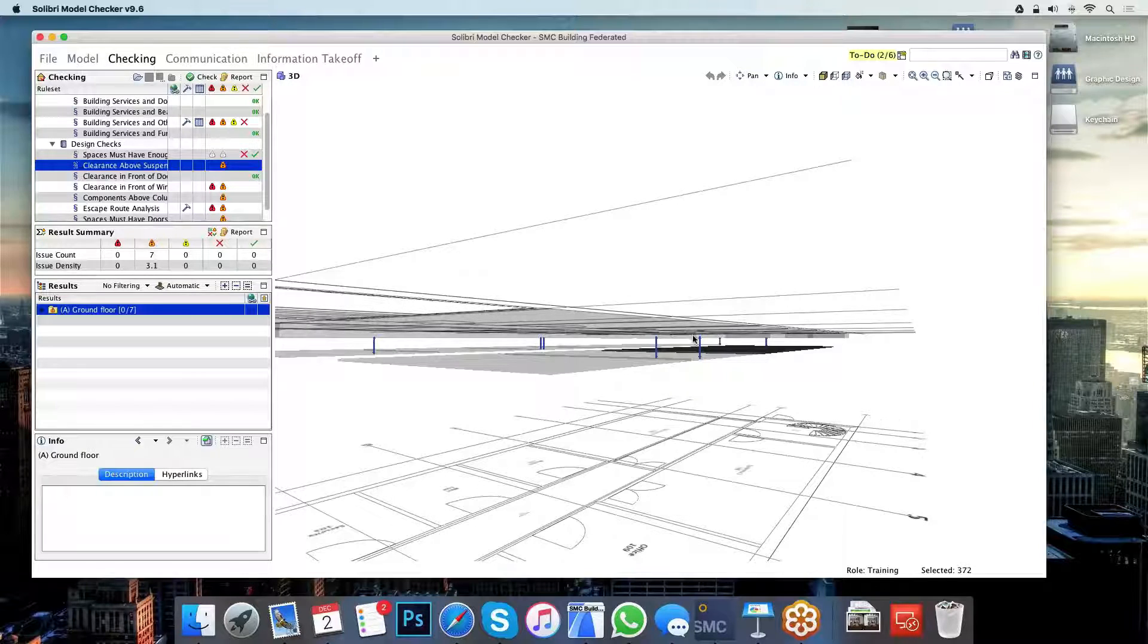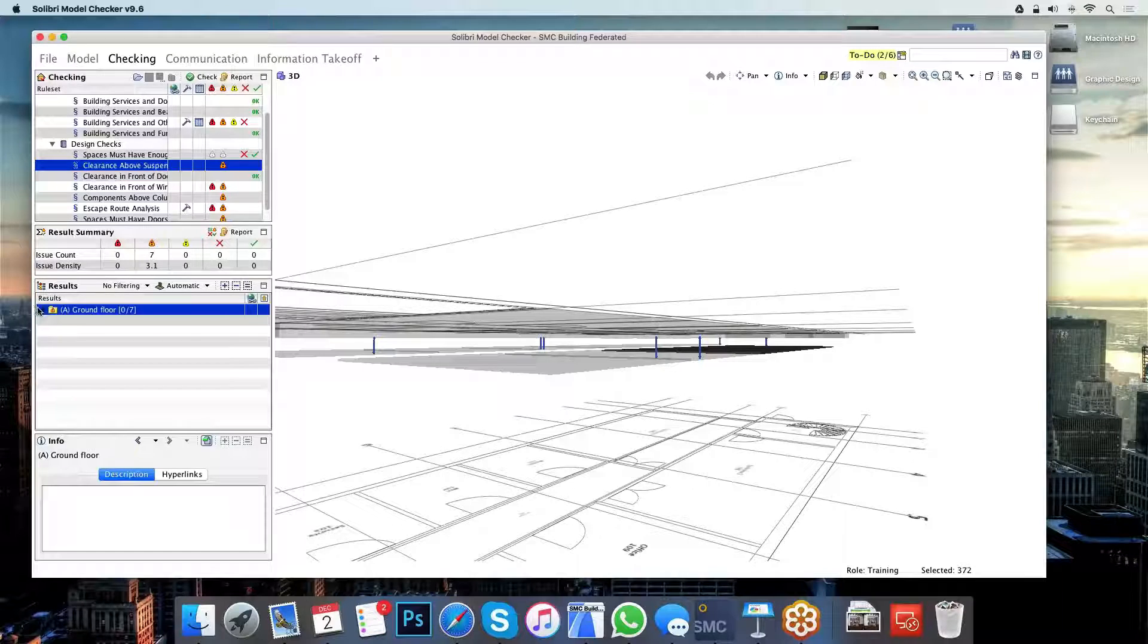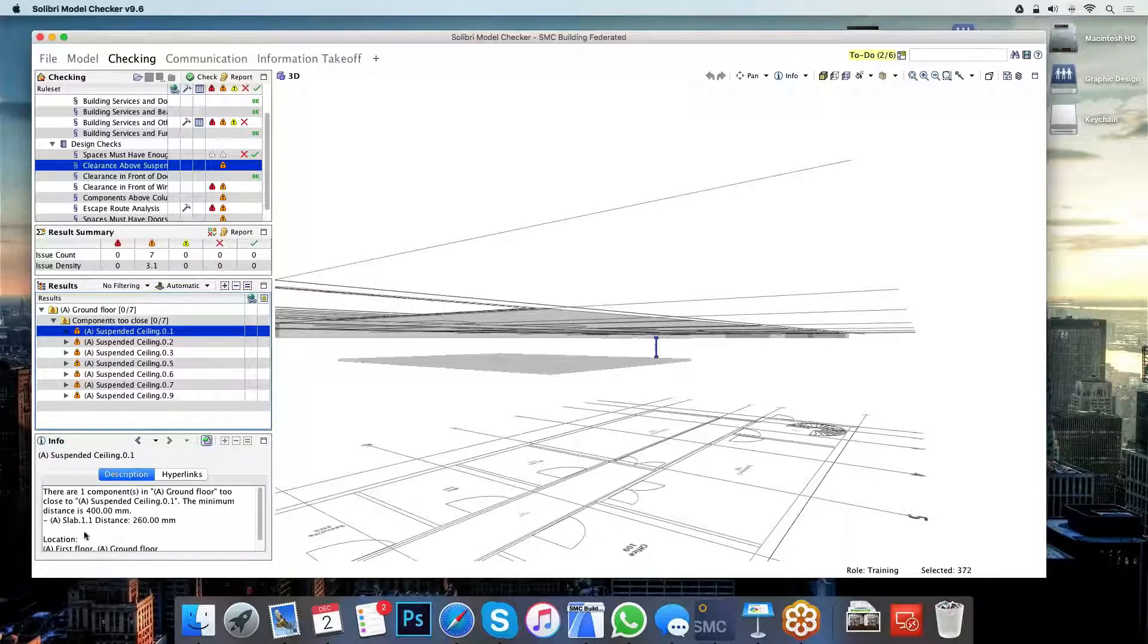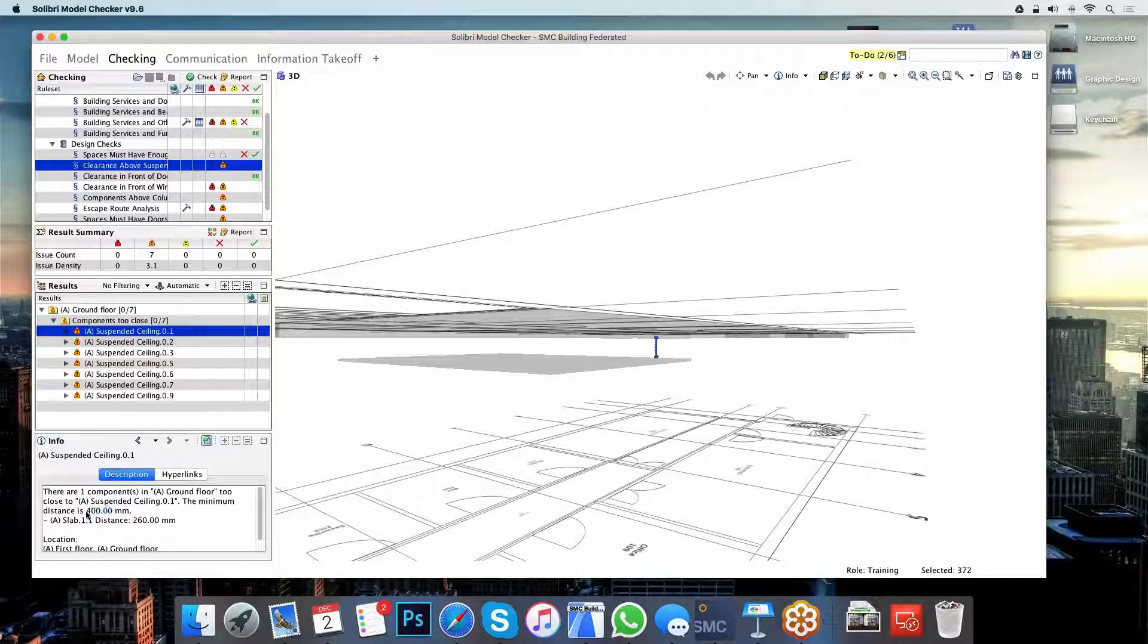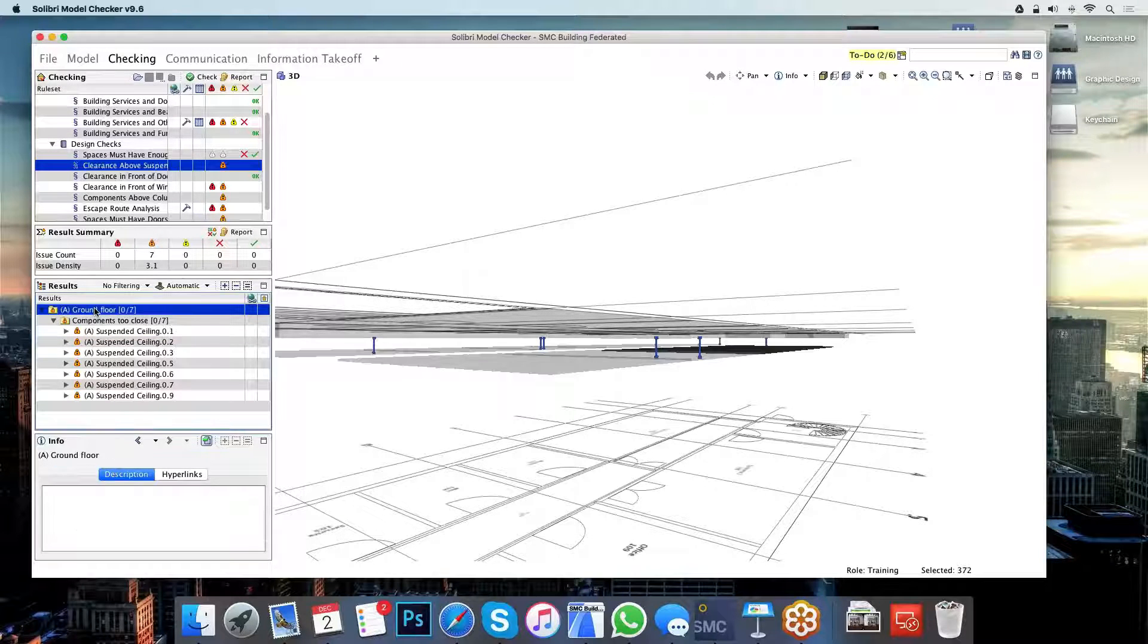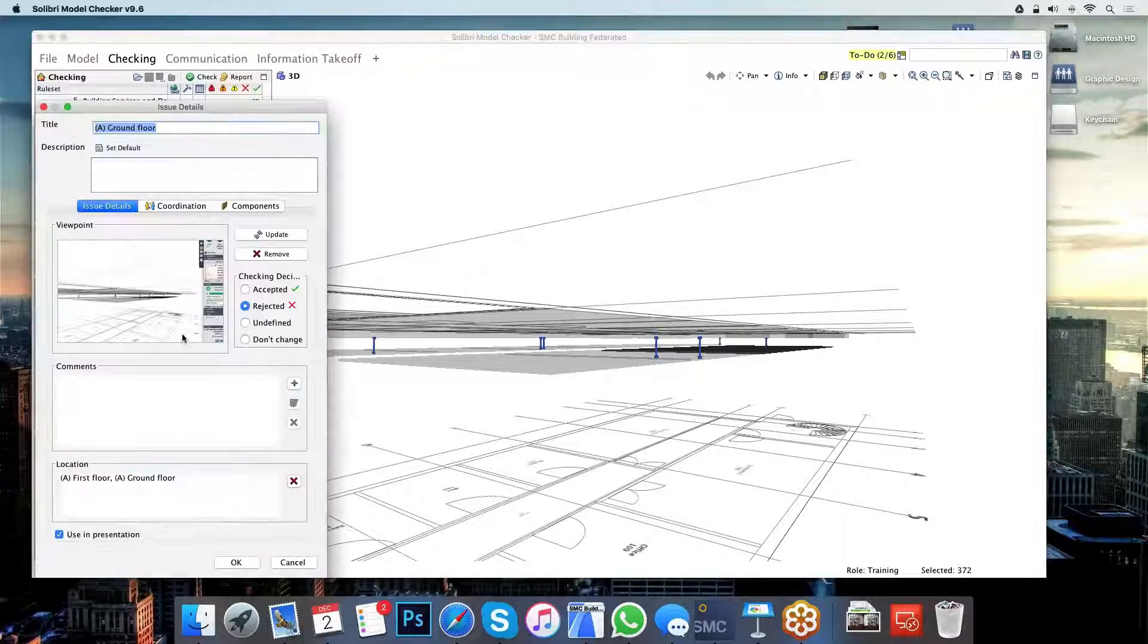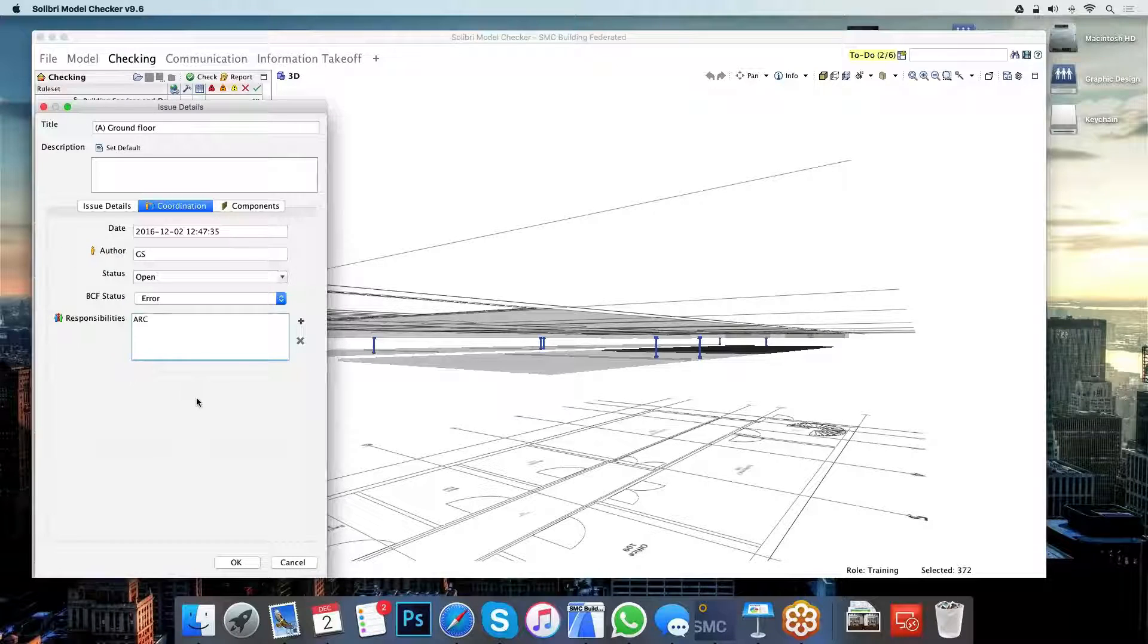However, it might slow us down because the contractor's hand is not going to fit in easily between these elements. Solibri is also able to tell me what the actual distance is between the elements. So I can see here that I have specified that there should be at least 400 mm between the elements, but in reality there's only 260 mm between here. So this is something I need to consider either during programming or maybe dropping the ceilings a little bit if I need to be able to keep up with the program. So again, I can simply send this back to the architect for his consideration.